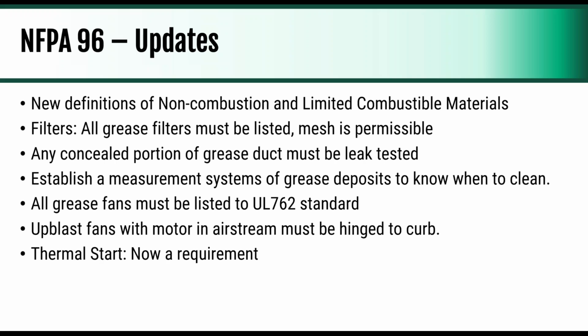This is actually a really good thing in our viewpoint because one of the bigger issues you have with kitchens is if somebody doesn't turn on the exhaust system and starts cooking, that heat builds up in the hood and it triggers the fire suppression system. That's not a fun thing, it's not a cheap thing, and it's not a quick thing to clean up. So now, if there's heat in the hood, the exhaust system should start automatically.